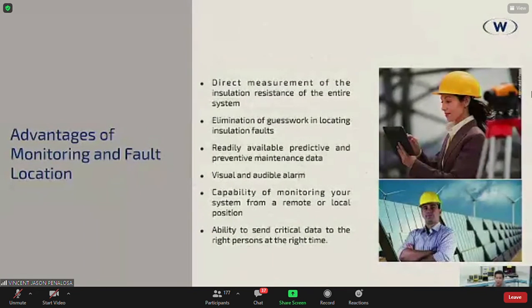I am almost done, but what are the advantages of monitoring and fault location? First, you have direct measurement of insulation resistance of the entire system. It eliminates the guesswork in locating insulation faults. You have readily available predictive and preventive maintenance data, so it's kind of like the first step for asset management. You can have a visual or audible alarm. You have the capability to monitor your system from a remote or local position, and you will have the ability to send critical data to the right persons at the right time. Whenever you connect it to a gateway, although none of my customers ever used it, it can send out a text message or up to 10 emails, but usually it's 2, 3 emails. So it can get that information to the right people at the right time.